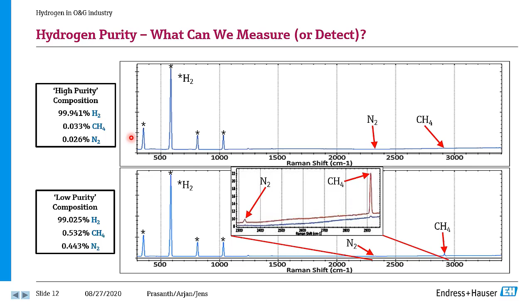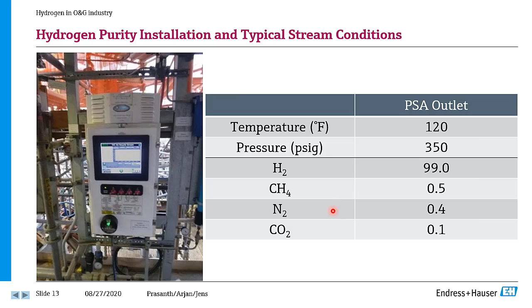The picture what you see here is an installation in a refinery in the US where our Optograph, which is based on Raman spectroscopy based on the scattering principle, is installed, and what you have from the PSA outlet is the numbers what you see in here: hydrogen 99, methane 0.5, nitrogen 0.4, and CO2.